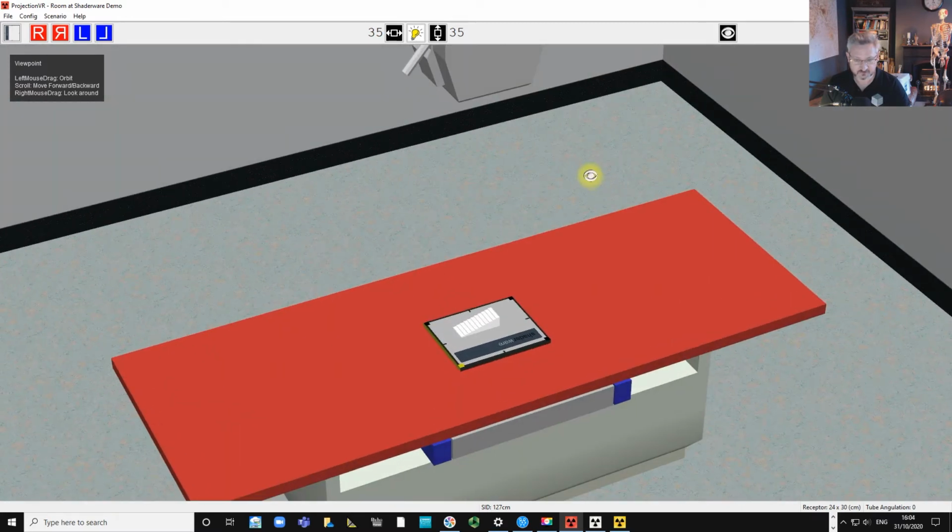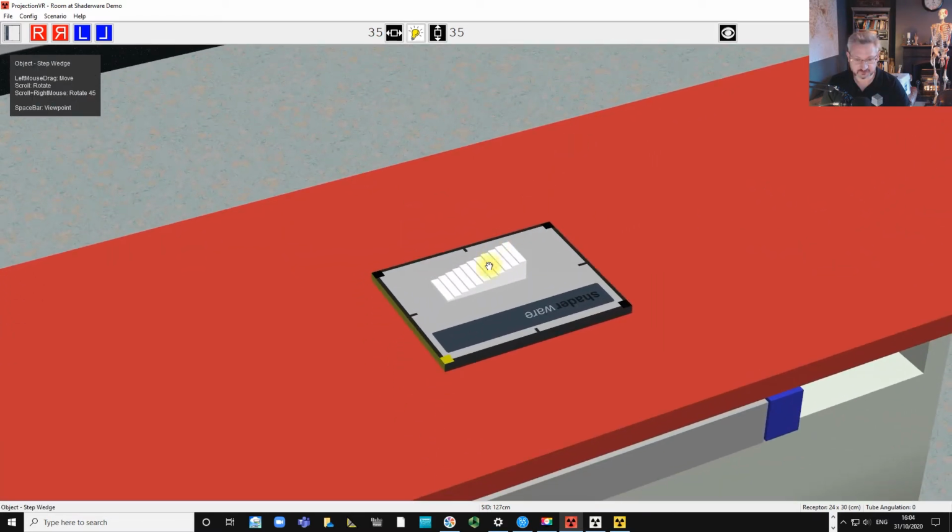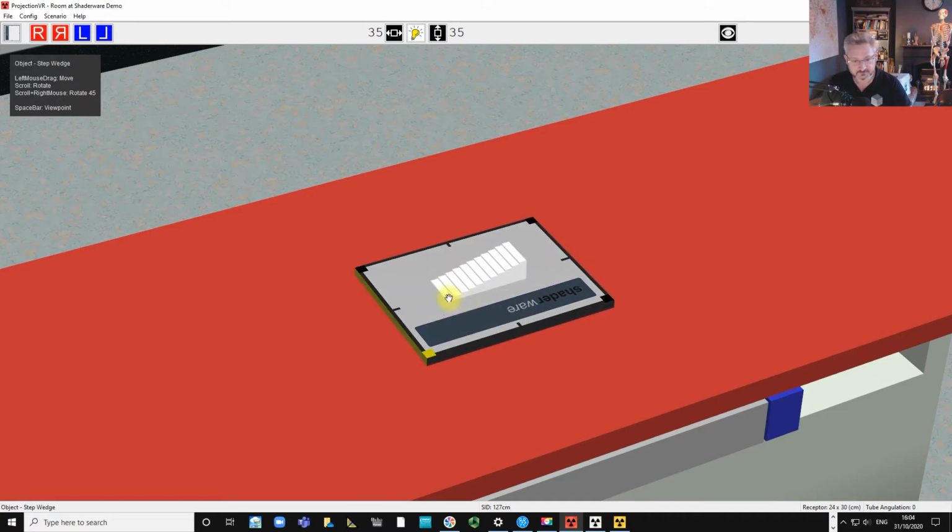So this is a common thing that you'll see in X-ray departments that radiographers and physicists use. So what we've got is a piece of aluminium that's been machined so that it's got 11 steps in it, and each one of these steps increases by the same thickness of aluminium. So as we X-ray this, obviously the photons that have to go through this thick bit will get more attenuated than the X-rays that go through the thinner bits. And so we should see different shades of grey depending on how much attenuation those steps attenuated the beam.